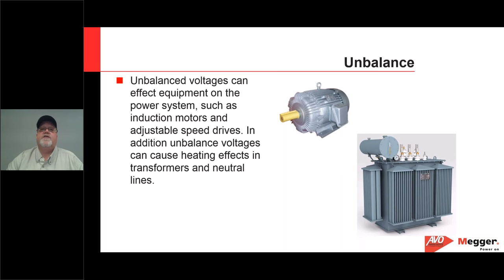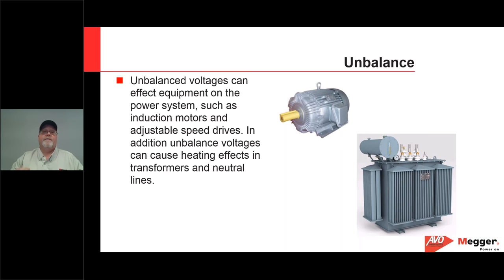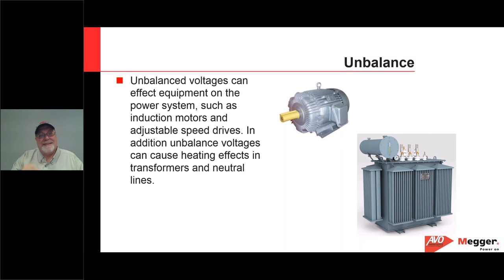This is one of the key issues and why you want to keep voltages well-balanced in your systems. When performing unbalance tests, look at the negative sequence unbalance and make sure it's less than 2% — that's typically the standard used today.